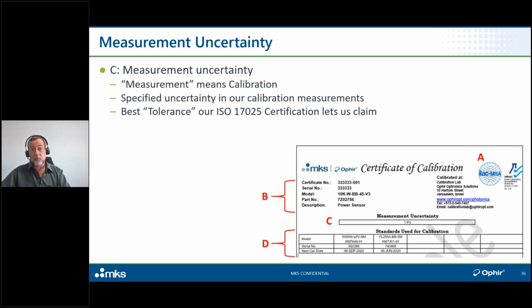If the measurement uncertainty really were in fact 0, and then the calibration result, the deviation that we measured in the calibration process between the sensor being calibrated and the master were, let's say, 1.5% low, then we would know with 100% certainty that the sensor being calibrated is exactly 1.5% below NIST in that particular measurement. In the universe we live in, that can never happen. There are uncertainties even in the NIST calibration itself. There's transfer error from the NIST reference to the working reference, setup instabilities, and so on. So the sensor being calibrated might be off from the truth by more or by less than the deviation that we actually measured when we calibrated it.